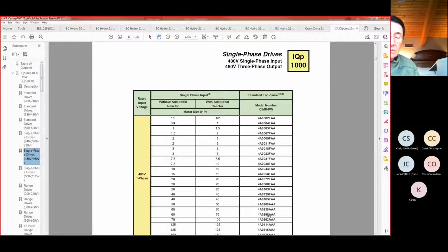because now we're severely imbalancing the load on the diode bridge. Two of the six diodes aren't even conducting. And the DC bus ripple, as a result, is much greater. Therefore, the capacitors are working much harder. Failure to do this risks the overheating of the capacitors and the overheating of the diodes. In my experience, in single-phase applications, the capacitors are the first ones to go.